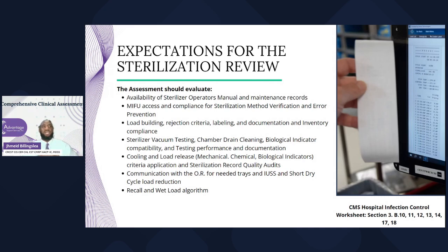Are you performing daily sterilizer vacuum testing when you're using steam, chamber drain cleaning, biological indicator compatibility, testing performance and documentation, right? The cooling and load release criteria. Can your team say these are the load criteria factors as recommended by AAMI, right? And who's doing the sterilization record quality audits?